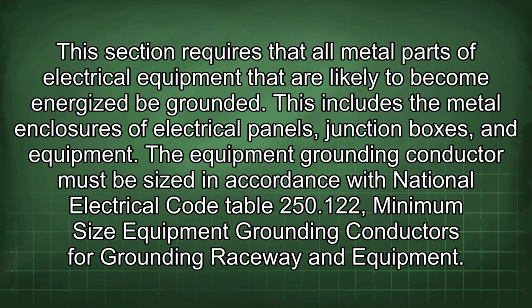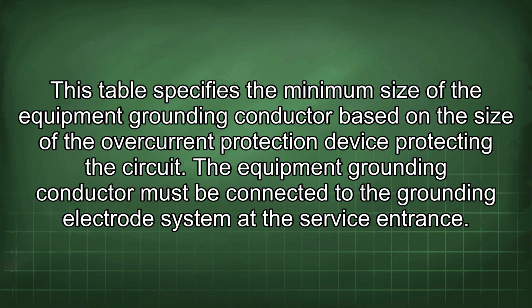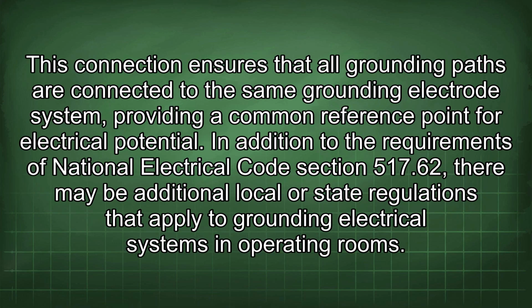This section requires that all metal parts of electrical equipment that are likely to become energized be grounded. This includes the metal enclosures of electrical panels, junction boxes, and equipment. The equipment grounding conductor must be sized in accordance with National Electrical Code Table 250.122, minimum size equipment grounding conductors for grounding raceway and equipment. This table specifies the minimum size of the equipment grounding conductor based on the size of the overcurrent protection device protecting the circuit. The equipment grounding conductor must be connected to the grounding electrode system at the service entrance. This connection ensures that all grounding paths are connected to the same grounding electrode system, providing a common reference point for electrical potential.